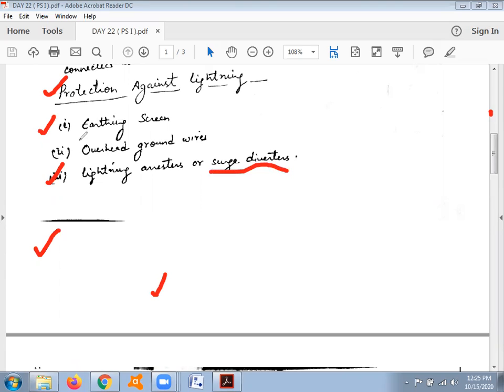The earthing screen provides protection to substations by providing a network of copper conductors overhead the equipment installed. The condition is that the network of copper conductors connected to earth at both ends should have minimum resistance, so that in case of overvoltage or overcurrent it can easily be grounded. The limitation of earthing screen is that it cannot protect against switching surges or traveling waves — it only protects against direct lightning strokes.